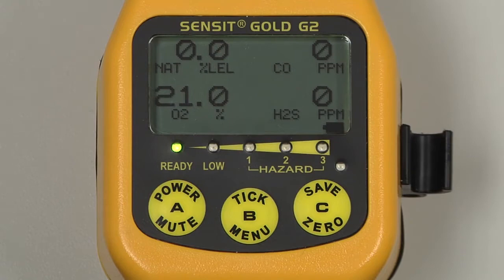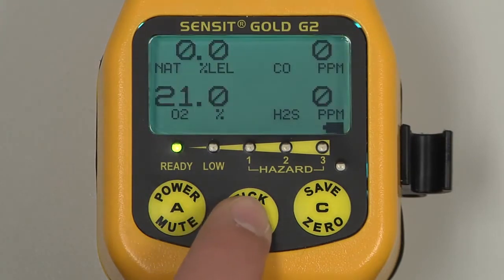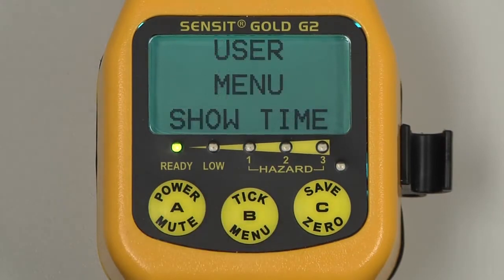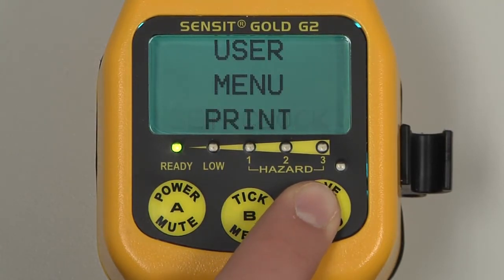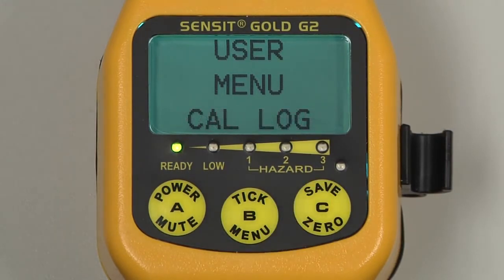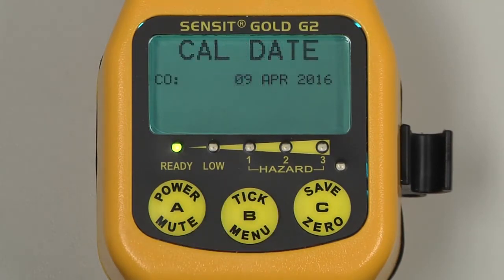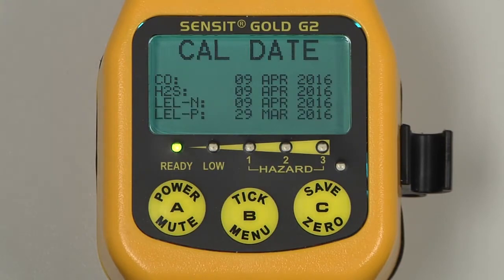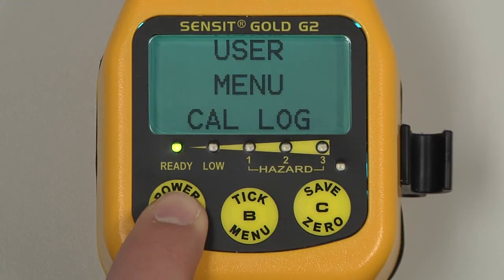To verify the calibration date, enter into the user menu by pressing and holding the B button until user menu is displayed, and scroll through this menu by pressing and releasing the C button until cal log appears. Select by pressing and releasing the B button, and a list of the most recent calibration date for each sensor or gas type will be displayed. We can exit out of this by pressing and releasing the A button, and again to return to the working display.